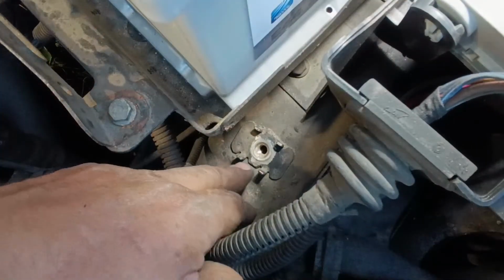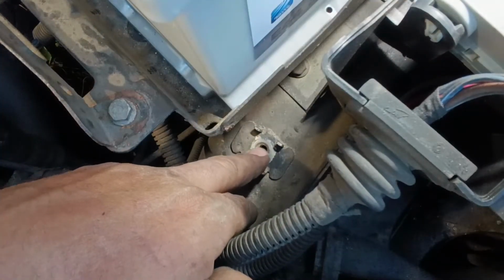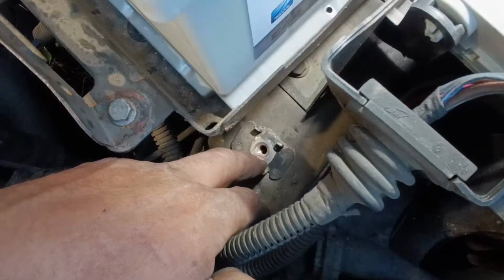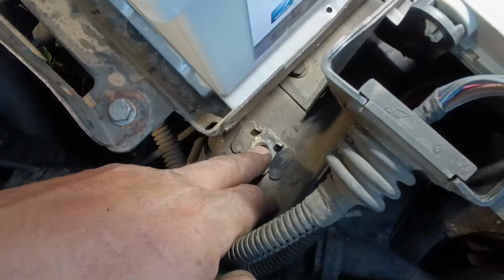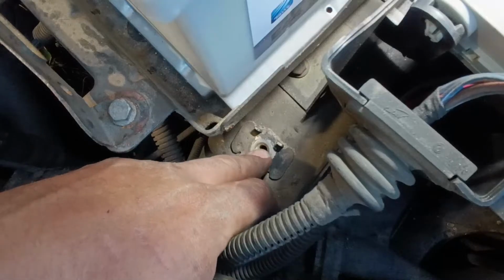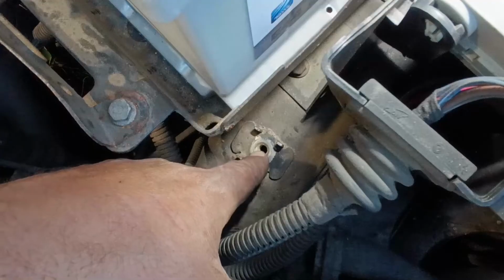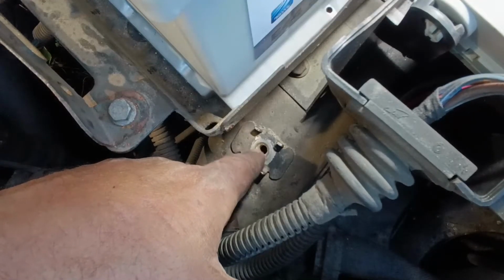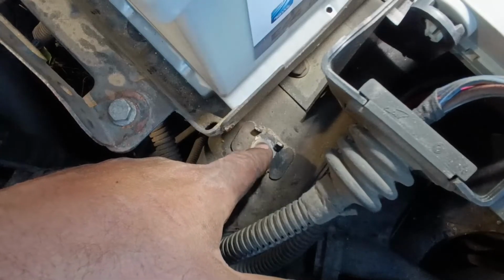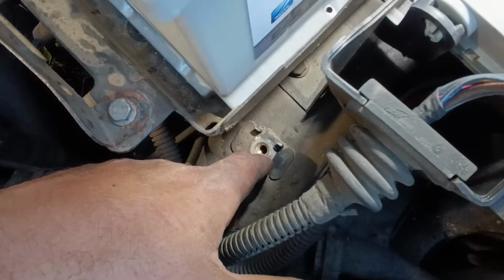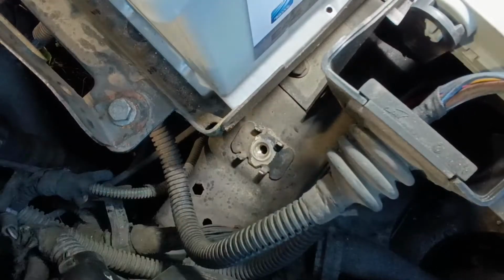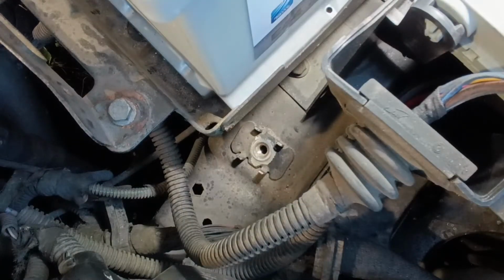Normally the conduction is made by the threading of the bolts, okay? And this area over here does not need to be bare metal, but it is best to be bare metal. Then we have to protect it, because we just removed the paint. So we have to use some ceramic paste grease, for example, that I like to use, and is very good, and does a better job than this appears to be.